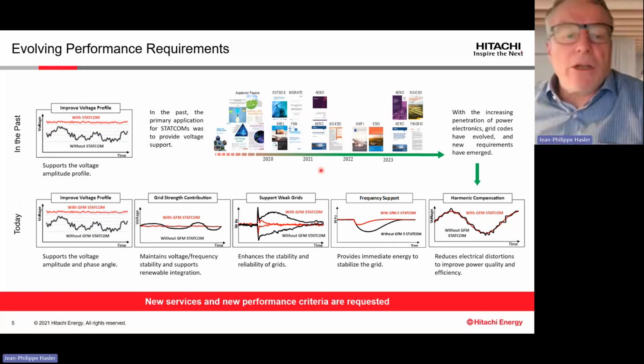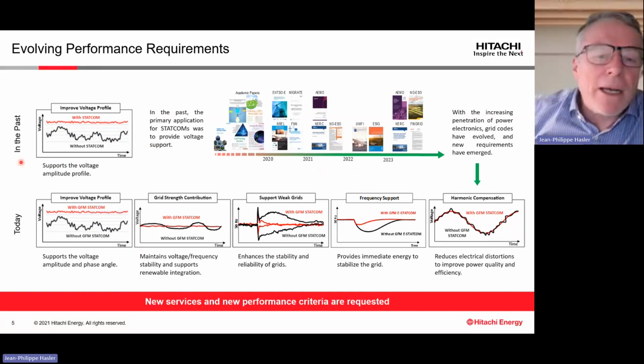Now, just to mention a bit more, what was the challenge for the STATCOM in the past? The only challenge was to improve the voltage profile. Voltage profile means the mean value of the voltage. It was not a challenge to compensate for small variations. That was in the past the purpose of a STATCOM, and normally it doesn't mean to maintain the voltage. It was necessary to use the STATCOM, but we have also used SVC technology, which is a TCR and a filter.